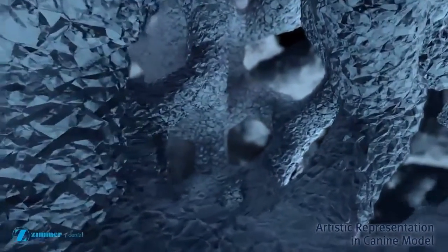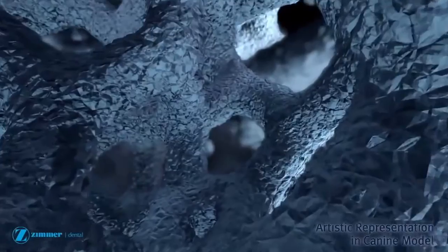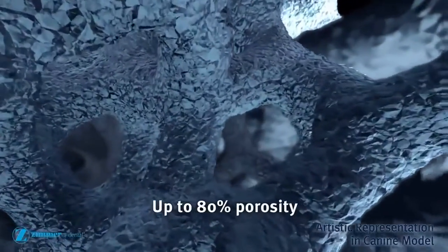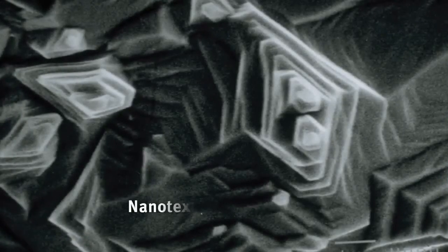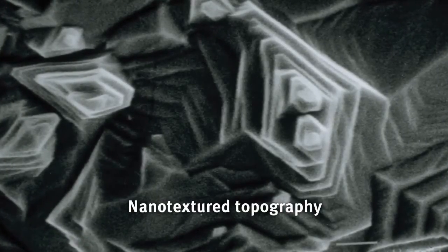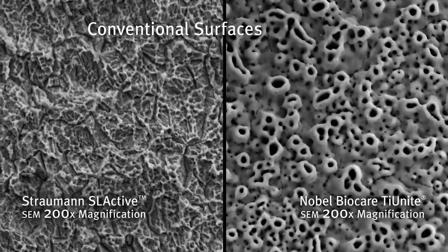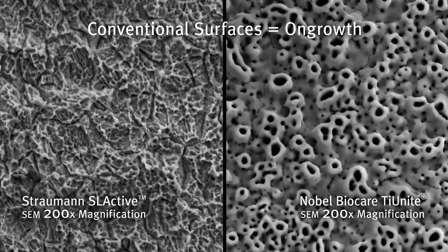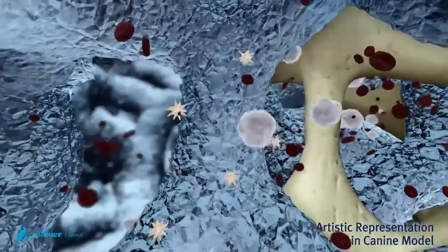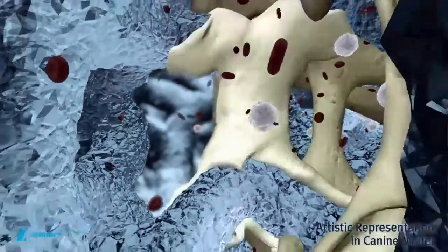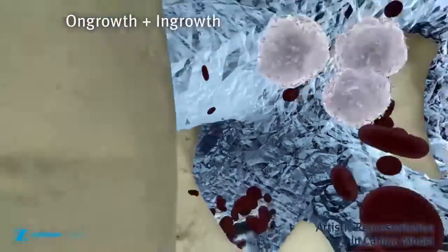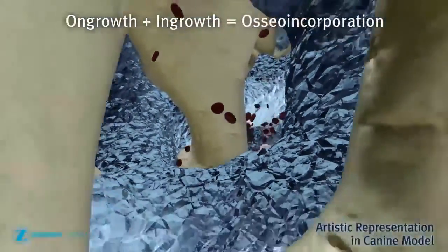A glimpse inside trabecular metal material reveals its uniform three-dimensional cellular architecture with up to 80% porosity. The entire surface area of trabecular metal material exhibits a nano-textured topography. Conventional textured or coated implant surfaces achieve bone-to-implant contact or on-growth. However, trabecular metal material's consistent, open and interconnected network of pores is designed for both bone on-growth and bone in-growth, or osseo-incorporation.